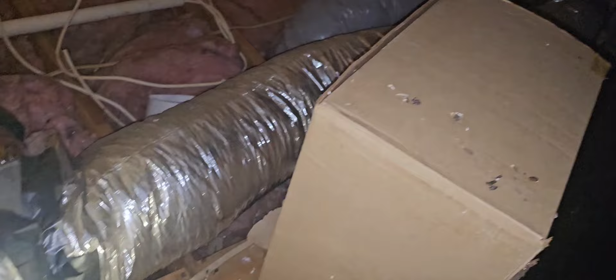So with that one dropping about 80 to 100, then the next drop is technically that one, but then it's got to travel way down there. Then this Y's off to somewhere over here. Everything from after that vent, everything down here just has nothing going to it downstairs. I got no airflow at all. So this is another 3-ton unit on a 2,000 square foot house. That's just great. I don't know what year this was born, but it does not have the greatest setup. I can't believe it, I can't see it being that tight.